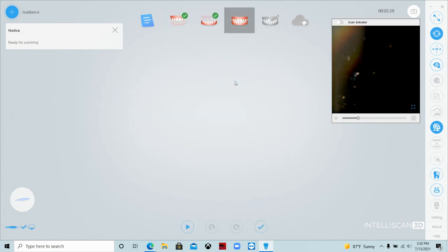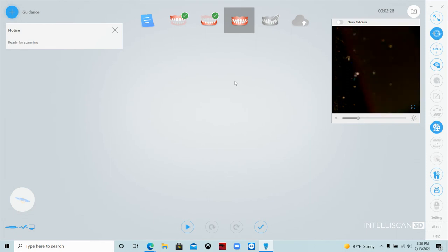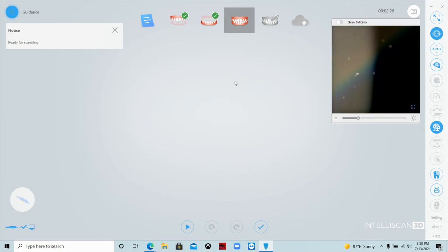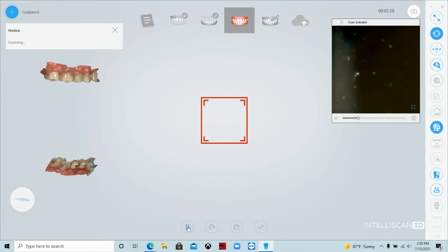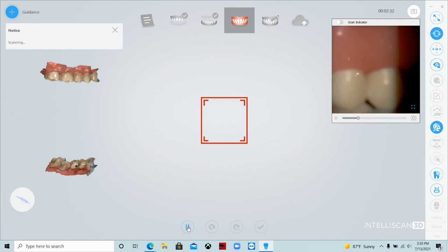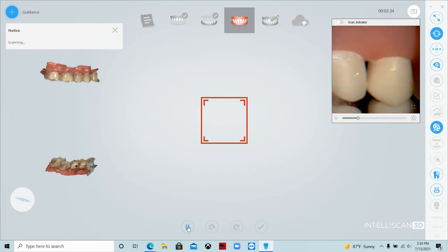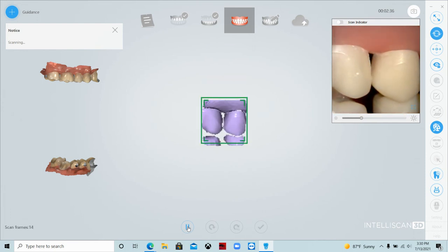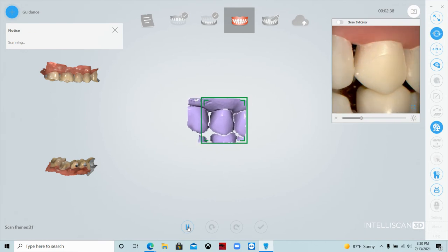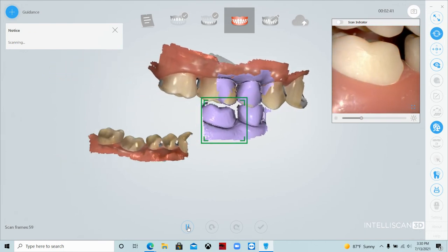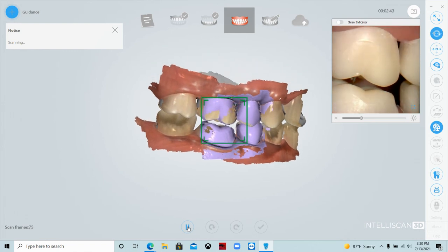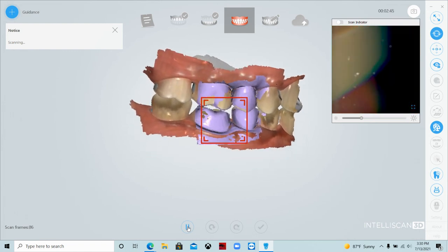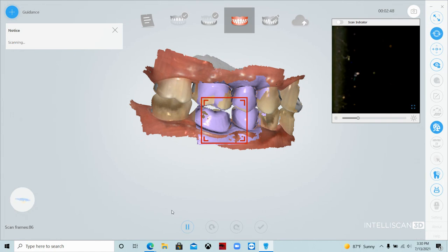Now you see at the top of the page, it went to the bite. I'm going to have the patient close down and I'm going to hit the start button for the bite. It's very quick and simple. You can see the arches on your left. You're going to simply scan a small square covering the gingival margins on the top and the bottom, a small square. I like to do between the first molar and the second premolar. I'm finished.